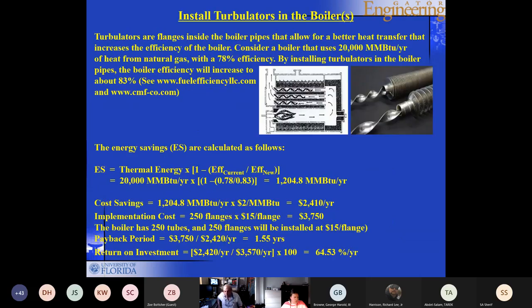Another one is installing turbulators in the boilers. These turbulators are basically flanges inside the boiler pipes. They allow for better heat transfer that increases the efficiency of the boiler. In other words, you make the flow turbulent, so you disturb the flow, and as a consequence, you end up with a higher heat transfer coefficient and a higher heat transfer rate. If you consider a boiler that uses, let's say, 20,000 million BTUs per year of heat from natural gas, with a 78% efficiency, if you install these turbulators in the boiler pipes, the boiler efficiency will increase to 83%. You can check these 2 sources. I gave you 2 websites here to justify the increase from 78% to 83%.